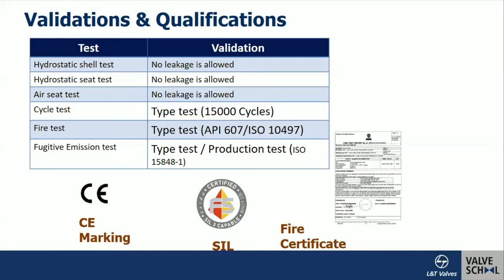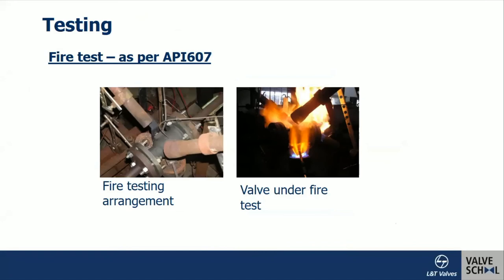Fugitive emission testing is now a standard requirement for all valves — multi-turn valves like gate and globe, and soft-seated valves like butterfly and ball valves. Emissions through the stem must be less than 100 ppm. Helium leakage testing is performed as a prototype test, and is also possible for production testing. Valves are also SIL-certified, as most valves today are used with actuators. The failure rate must be analyzed and must be well within the specified limit.